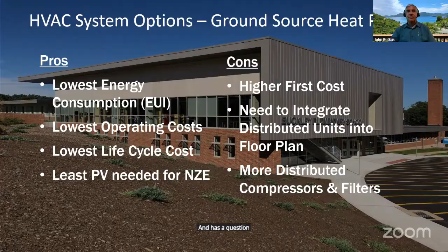That's what Randall was describing, that systems are designed based on a specific refrigerant. Right now we're using 410A as the refrigerant, and that's changing because it's being migrated out. This new charge, while it may work, won't work the way the system is supposed to as designed.